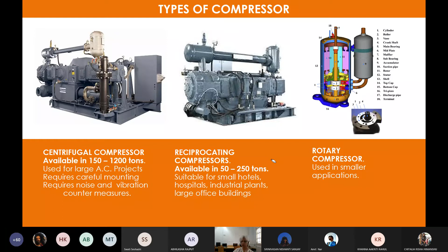So use for large AC projects requires careful mounting, requires noise and vibration countermeasures, so you will require acoustics, and you will require drainage and all that. Reciprocating compressors are a little lower in scale, that is 50 to 250 tons, suitable for small hotels, multiple banquet halls, or maybe even a small medium-sized building where 250 tons are to be applied for the entire building. You can go for this. And then you have rotary compressors used in smaller applications. So this is how the compressor goes.